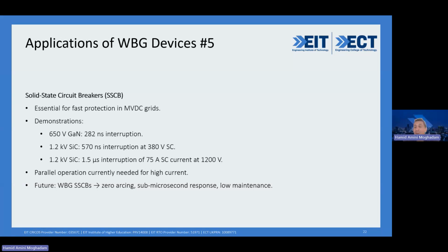As we discussed, power systems become faster. They become more complex. Okay, they need protection equipment that is equally fast, high performance. That's where your solid-state circuit breakers come in. Okay, they are essential for fast protection in medium volt DC grids. Some examples here for you from literature. A 650 volt GaN device could interrupt a short circuit current in 282 nanoseconds. How much faster they are. Compare that to milliseconds of an ordinary or traditional circuit breaker. Another used 1.2 kilovolt silicon carbide and showed 570 nanoseconds at the 380 volt short circuit, which is massive.